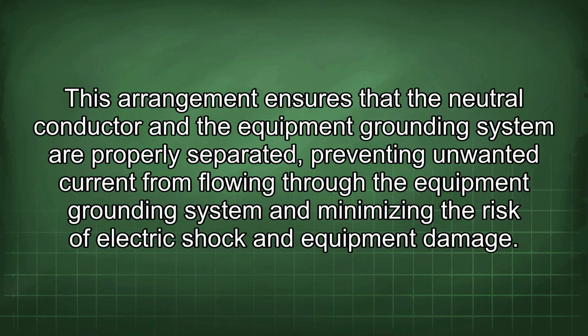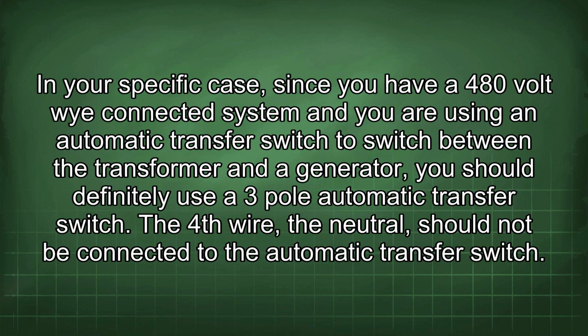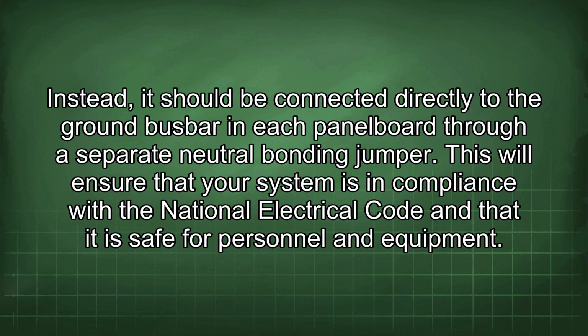This arrangement ensures that the neutral conductor and the equipment grounding system are properly separated, preventing unwanted current from flowing through the equipment grounding system and minimizing the risk of electric shock and equipment damage. In your specific case, since you have a 480-volt Y-connected system and you are using an automatic transfer switch to switch between the transformer and a generator, you should definitely use a 3-pole automatic transfer switch. The fourth wire, the neutral, should not be connected to the automatic transfer switch. Instead, it should be connected directly to the ground busbar in each panel board through a separate neutral bonding jumper.